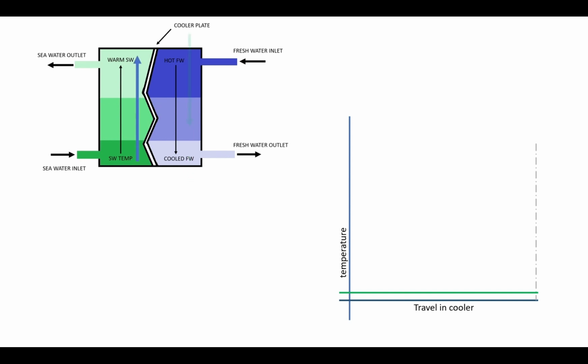Let's look at the cooling performance diagram of counterflow cooling. The vertical line represents the temperature of the fluid, while the horizontal line is the flow and travel of the fluid in the cooler. Cold seawater will enter the cooler and absorb the heat from fresh water until it leaves the cooler as warm seawater.